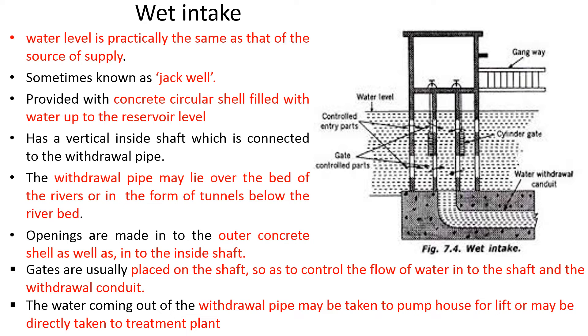The wet Intake structure is called a Jack well. Because it stores water inside, the water level in the well is the same as the water level in the source. It consists of a concrete shell filled with water, provided with a vertical shaft. Entry ports on the vertical shaft allow water in, flow control valves are provided at the top, and water is transferred to the withdrawal pipeline. The Jack well transfers water to the pump house and through the withdrawal pipeline to the water treatment plant.